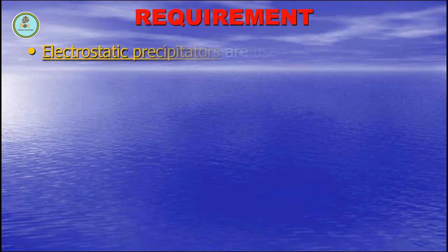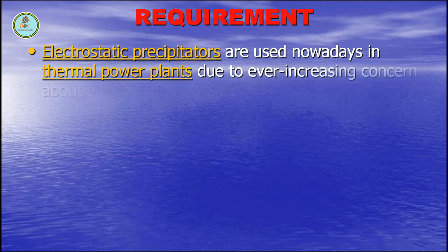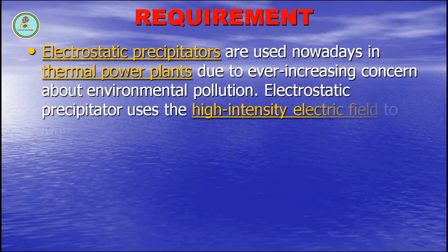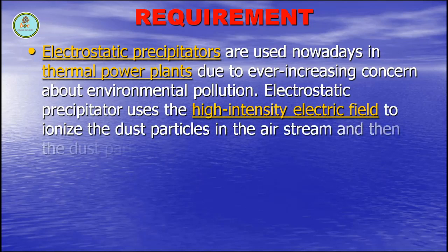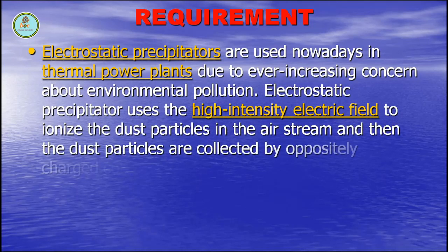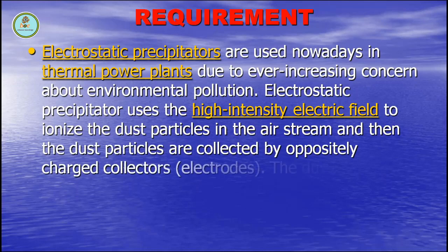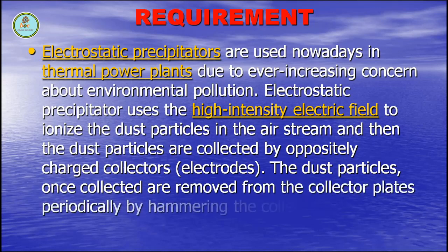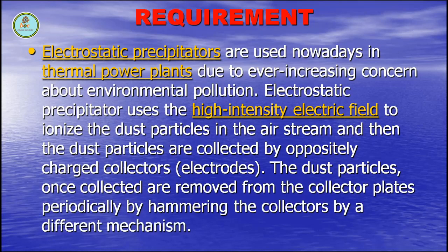Electrostatic precipitators are used nowadays in thermal power plants due to ever increasing concern about environmental pollution. Electrostatic precipitators use a high intensity electric field to ionize the dust particles in the air stream, and then the dust particles are collected by an oppositely charged collector. The dust particles once collected are removed from the collector plates periodically.